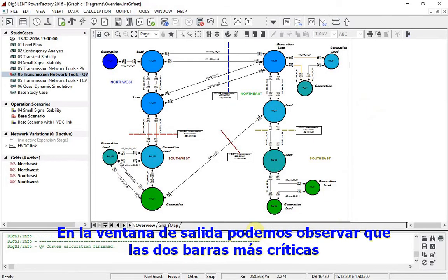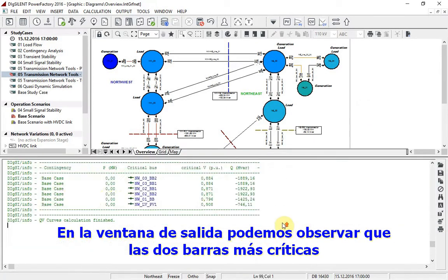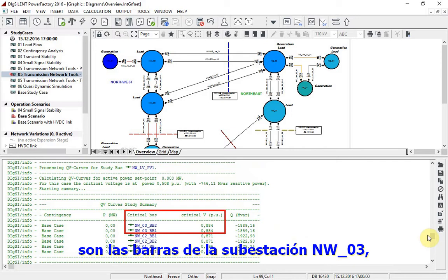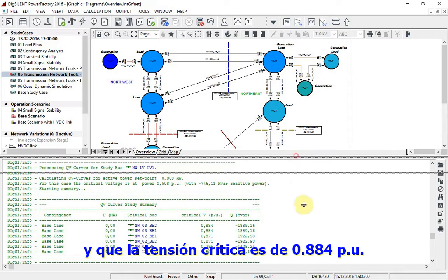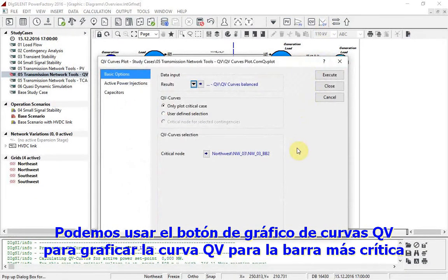In the output window, we can see that the two most critical busbars are those at substation NW03, and the critical voltage is 0.884 per unit. We can now use the QV curves plot button to plot a QV curve for the most critical busbar.